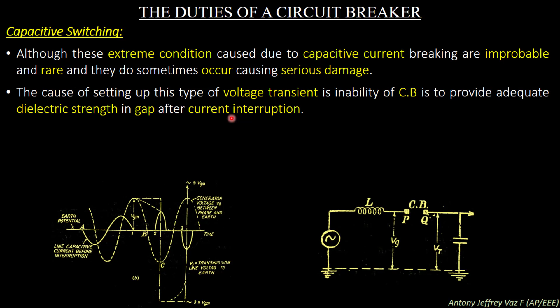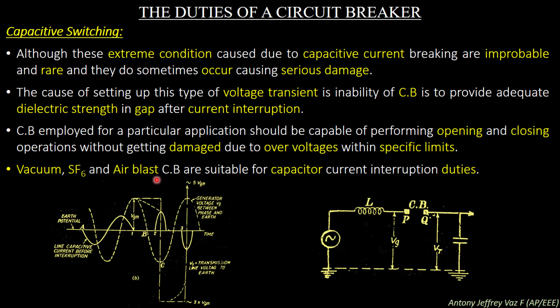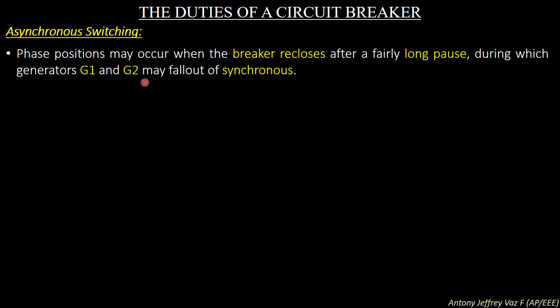Asynchronous switching. Phase position differences may occur when the breaker recloses after a fairly long pause, during which generators G1 and G2 may fall out of synchronism. You can see this is a very long transmission line or a power grid. There are two generating stations, G1 and G2. Similarly, the two generating stations have two different voltages, V1 and V2, which are connected to a long grid. So in a long grid, we have inductance and capacitance for the two systems, which are shown in the figure. You can see a circuit breaker is used to join these two power grids. So during such a condition, when there is a long pause interval, the generators G1 and G2 will fall out of synchronism.